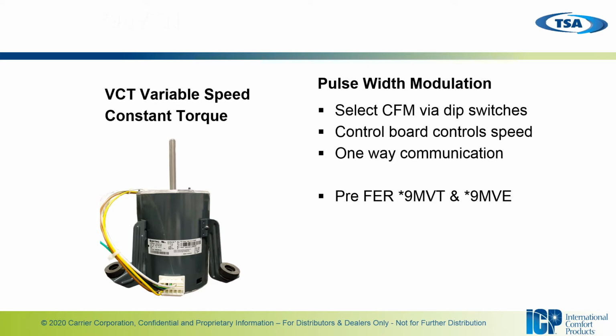So with this motor, your airflow is typically set up via dip switches on a control board. The control board will output the signal to the motor based on the mode and the stage that it's calling for. All of the programming for the speeds is in the control board, based on the dip switch settings. This is one-way communication, which means the control board sends the signal to the motor, and that's it. It's just a dedicated command to the motor. You would have seen these in the pre-FER furnaces in the G9 F9 MVT model and the G9 F9 MVE model.